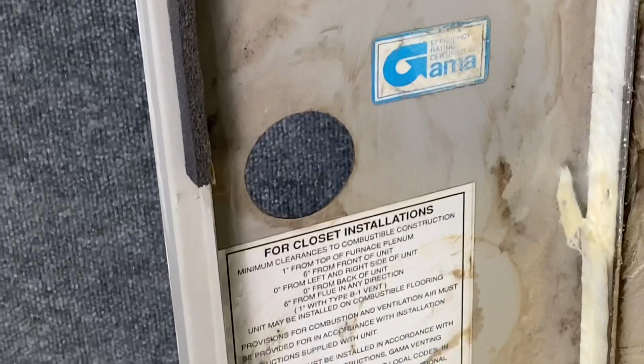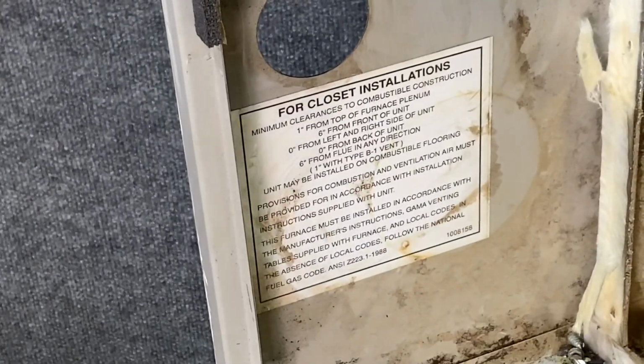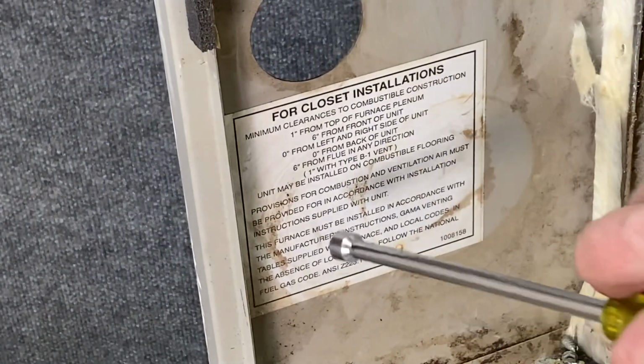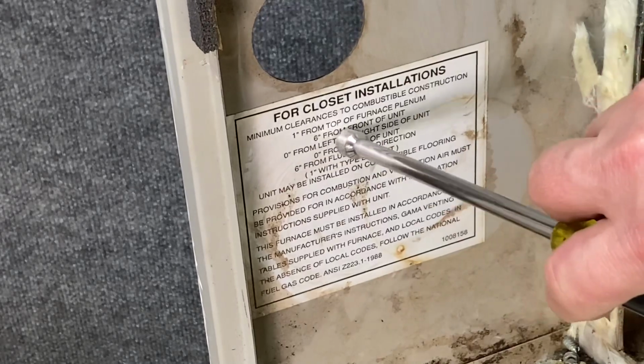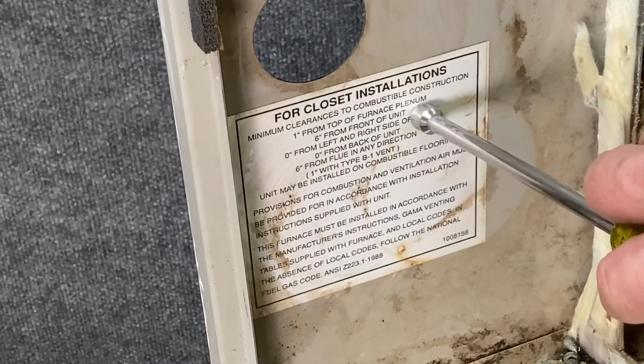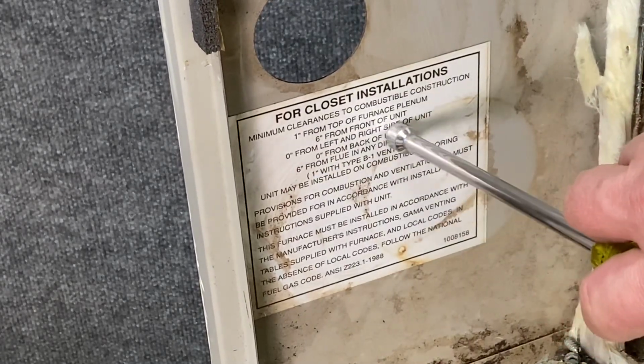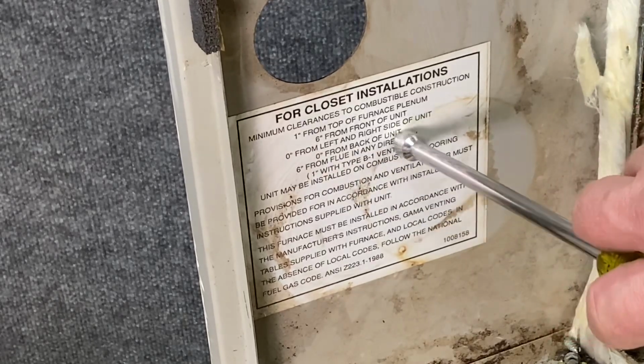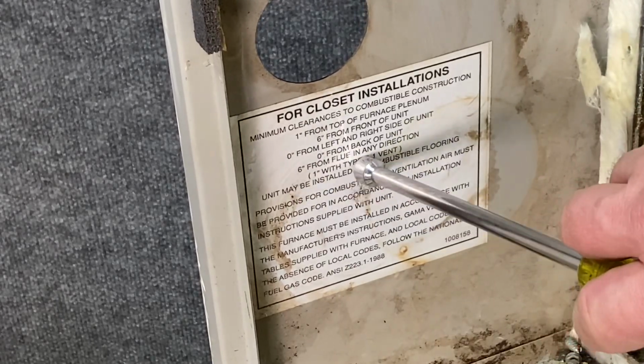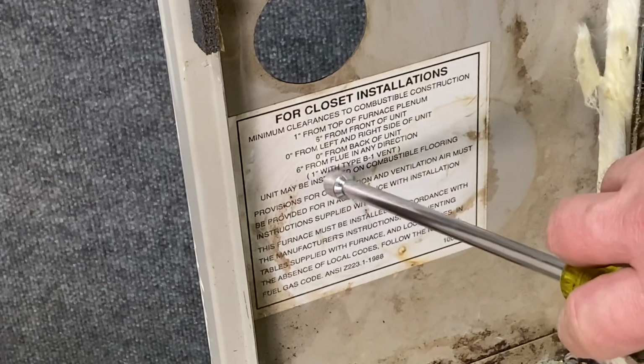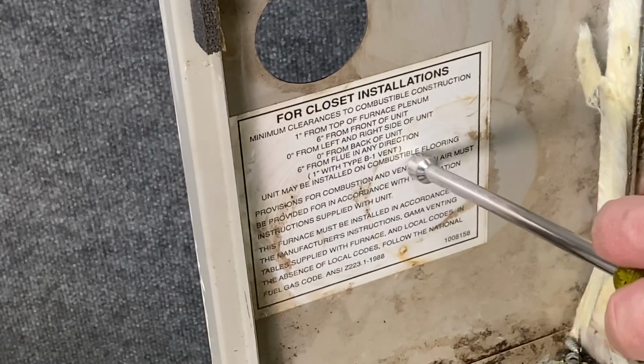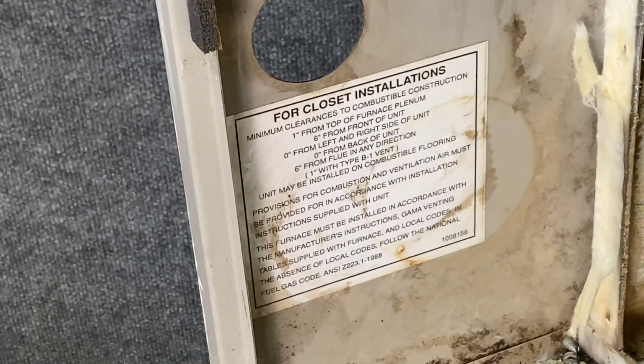On the bottom side, if we look down a little bit lower, it has more information connected to closet installation. So if we're going to install this in a closet, it has to be 1 inch from the top of the furnace to the plenum, 6 inches from the front of the unit, 0 inches from the left and right side of the unit, 6 inches from the flue in any direction, 1 inch with type B1 vent. So it gives you specifications of how close you can be.